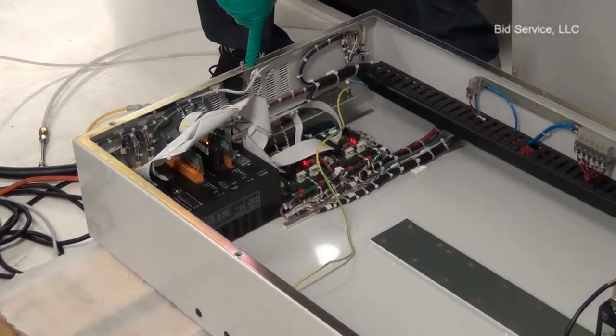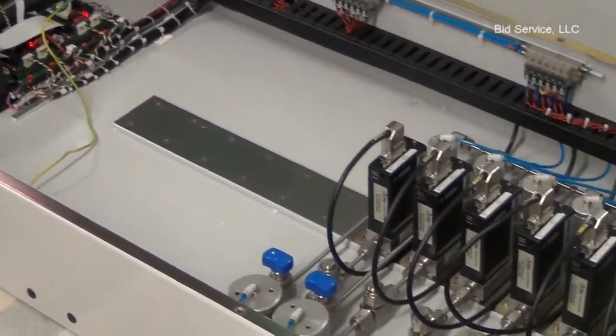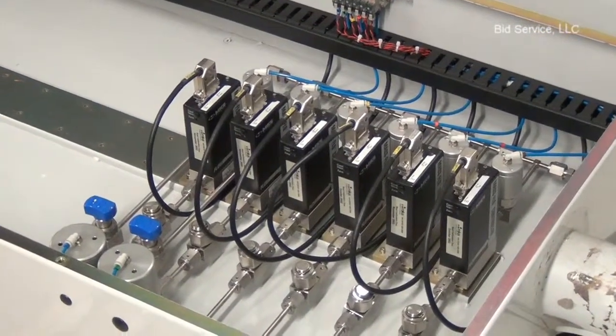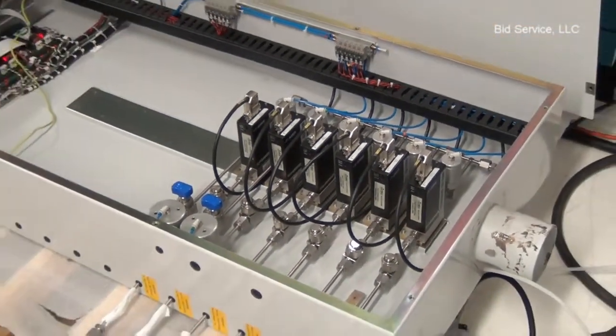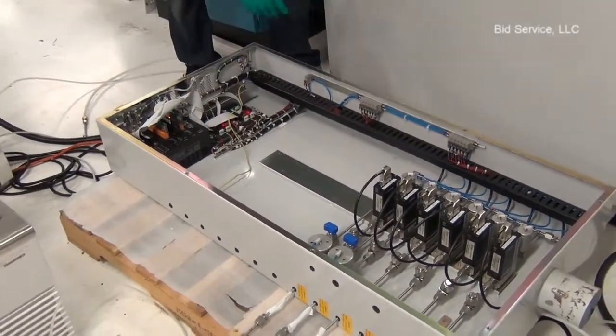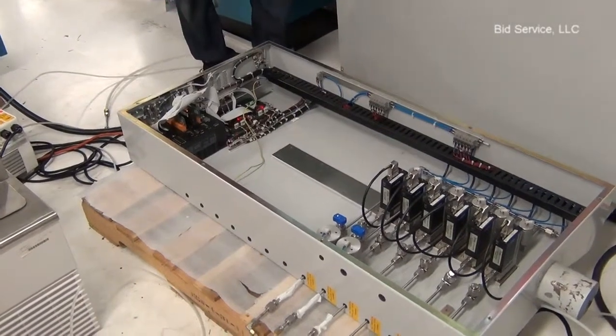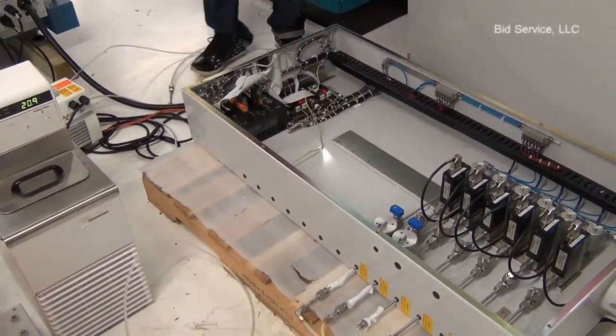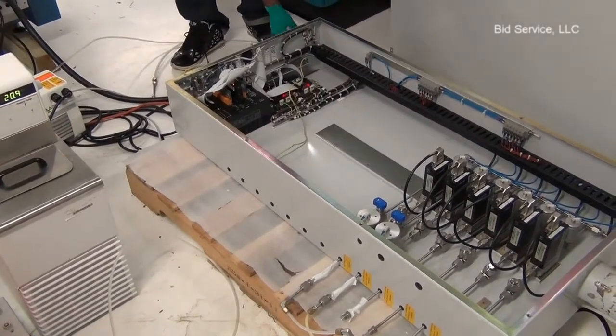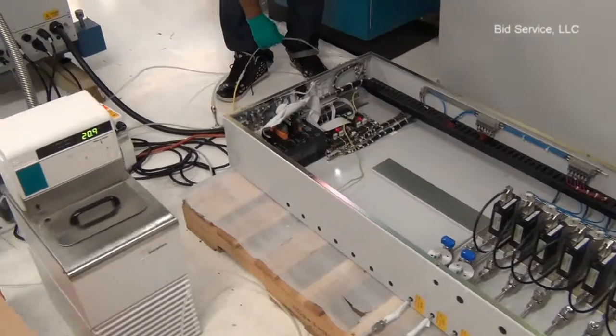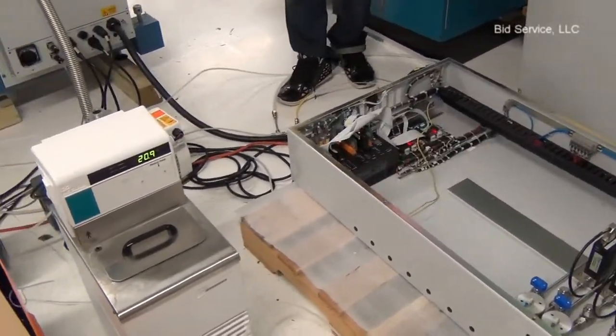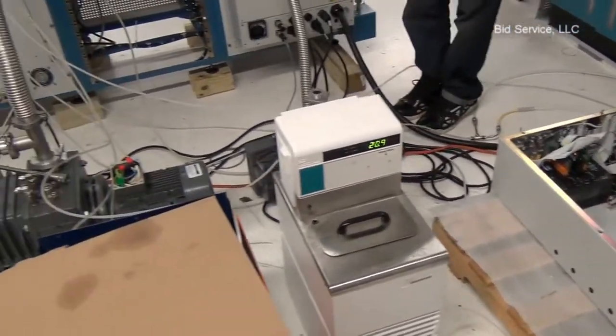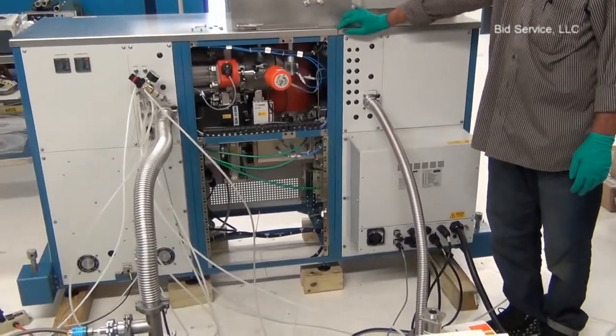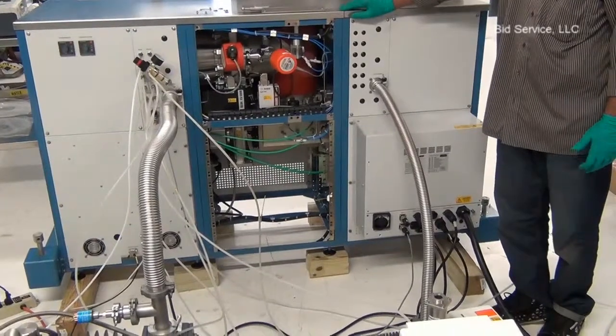This is the cover interlock and six mass flow controllers. This is interfaced to the PC via the PLC here. The gas pump needs compressed air to be connected, about 17 PSI. The main system also needs 70 PSI compressed air, and about 40-60 PSI, and helium at about 20-30 PSI.